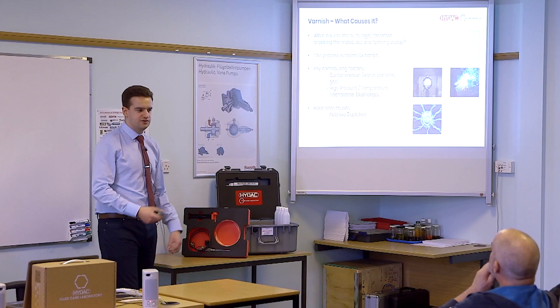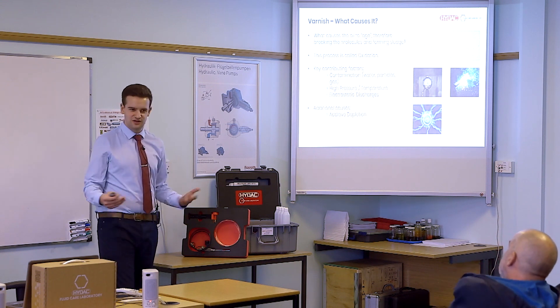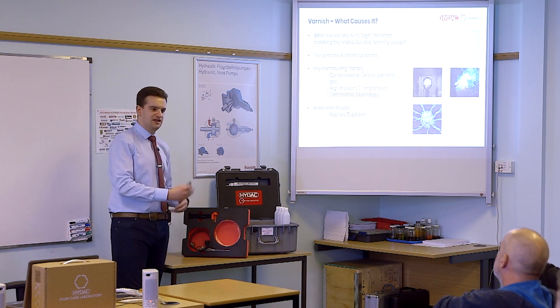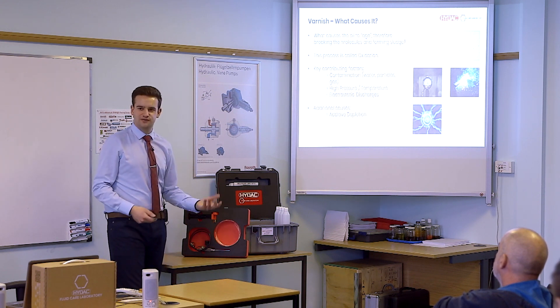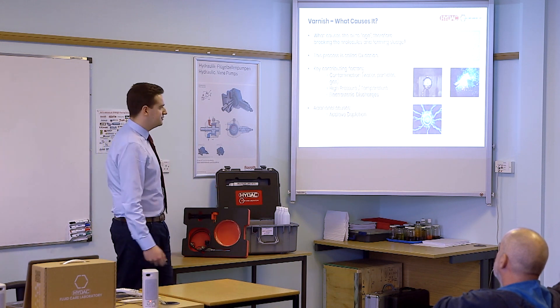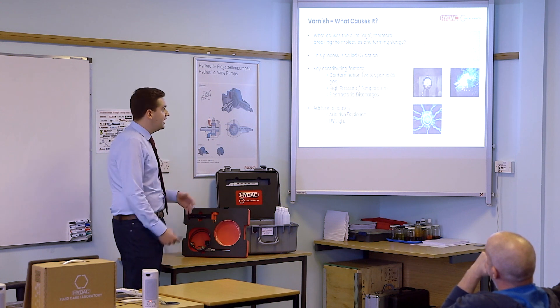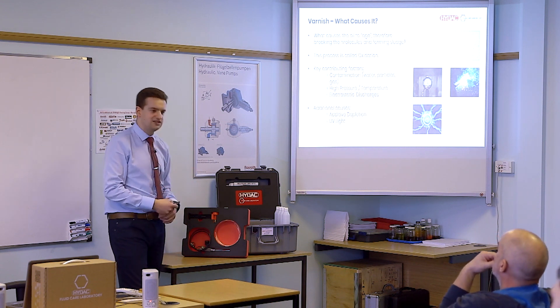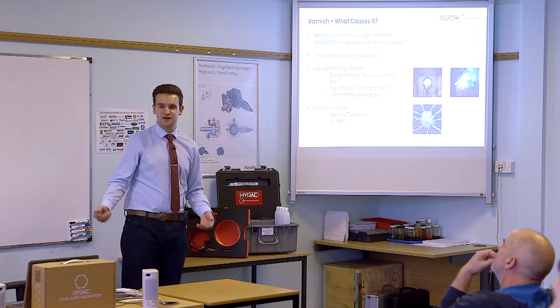We also have additive depletion. You have additives within your oil that will be focused on preventing oxidation from occurring — called antioxidant additives. Their job is to react with the oxygen and extend the lifetime of the oil. But if they get depleted and you run out of antioxidants, then your oil is going to be the focus of oxidation. UV light is also a factor. If you take a sample and leave it out in the sun for a few days or on the windowsill, even a bit of UV will contribute. We did some studies in-house where we left some samples hidden from sunlight and one out in sunlight — even within weeks we were going from good levels of oxidation to action and critical levels.